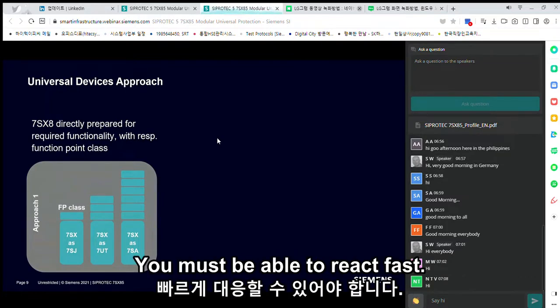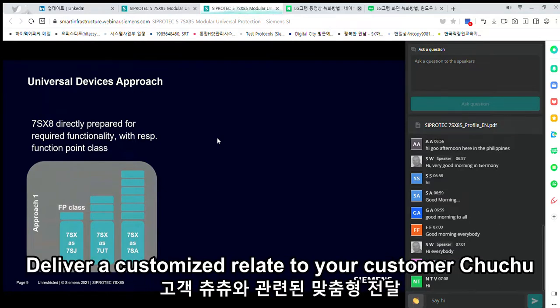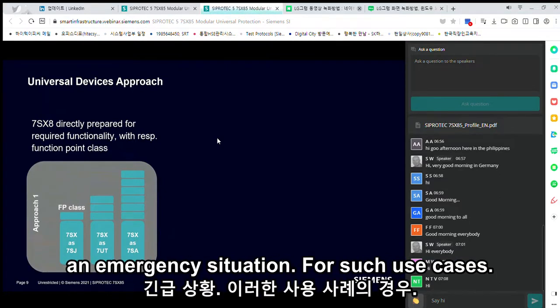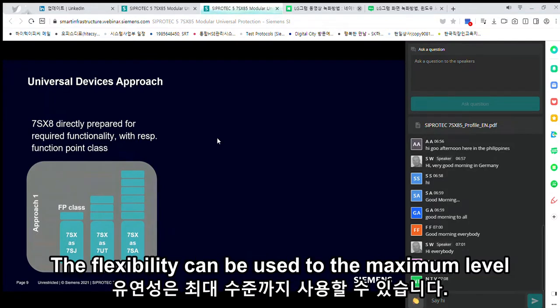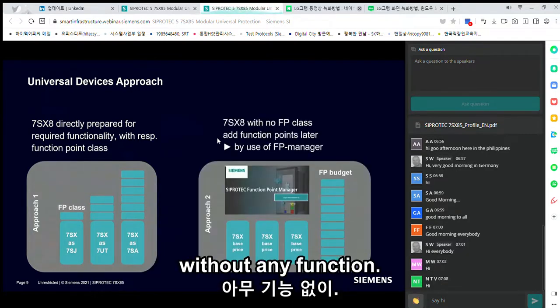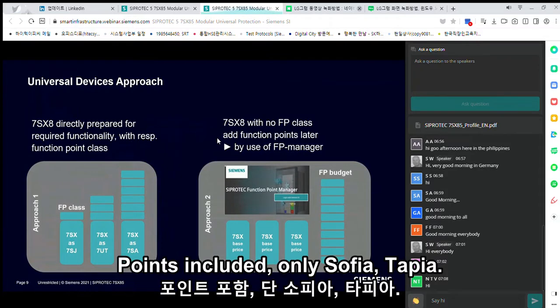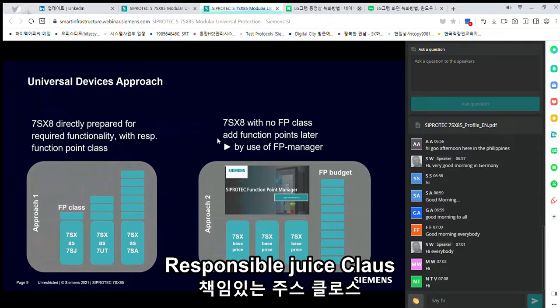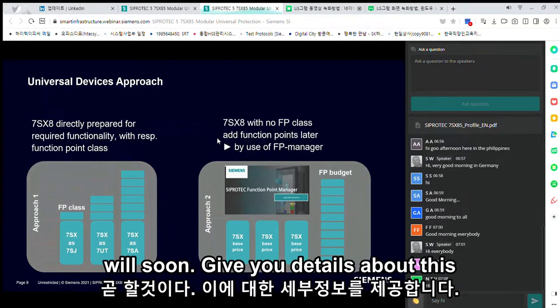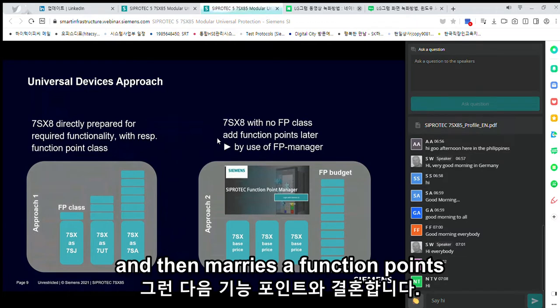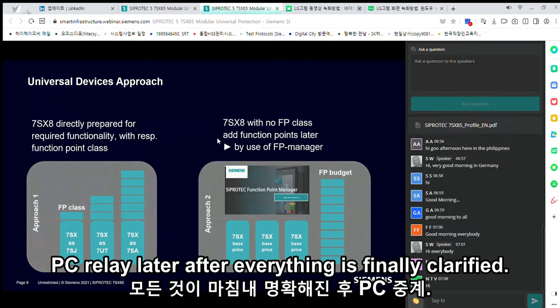Or you must be able to react fast to deliver a customized relay to your customer due to an emergency situation, but do not have all device types on stock. For such use cases, the flexibility can be used to the maximum level. You order the universal relay without any function points included, only the fitted hardware, base hardware and expansion modules. Klaus will soon give you details about this. And then marry the function points with the relay later, after everything is finally clarified.